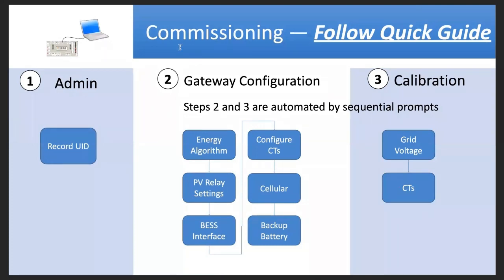So again, during commissioning, you want to follow the quick guide. The quick guide shows you all the steps for commissioning, and it will be covered in detail during the commissioning training. As far as your first step, you've got to record the UID and all of the customer information: the customer's utility, their address, and the customer's email for monitoring access. And then you would go in and configure the gateway, or the EMC itself, and set it up for whether it's self-supply or time of use, the energy algorithm, and a couple of the other settings.